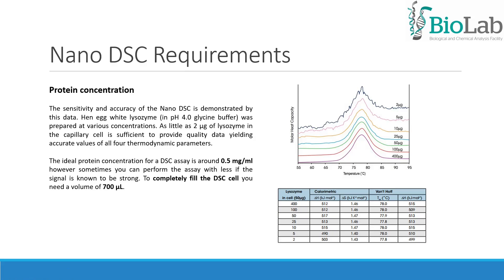Regarding NanoDSC requirements and protein concentration, the sensitivity and accuracy of the NanoDSC is demonstrated by this data. Hen egg white lysozyme in pH 4 glycine buffer was prepared at various concentrations. As little as 2 micrograms of lysozyme in the capillary cell is sufficient to provide quality data yielding accurate values of all four thermodynamic parameters. The ideal protein concentration for a DSC assay is around 0.5 mg per mL. However, sometimes you can perform the assay with less if the signal is known to be strong. To completely fill the DSC cell, you need a volume of 700 µL.